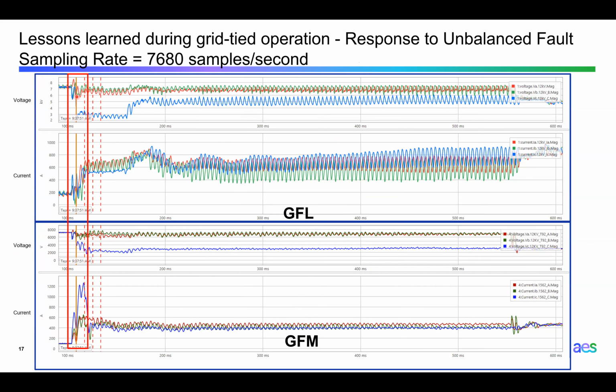In this transient response that you're seeing here in this red rectangle, you can see the differences in the magnitude of current. The grid forming inverter is pushing out an unbalanced current, whereas if you look at the grid following inverter in this transient period, it's pushing out almost like a positive sequence. You don't really notice any kind of difference between A, B, and C phase in this transient period.